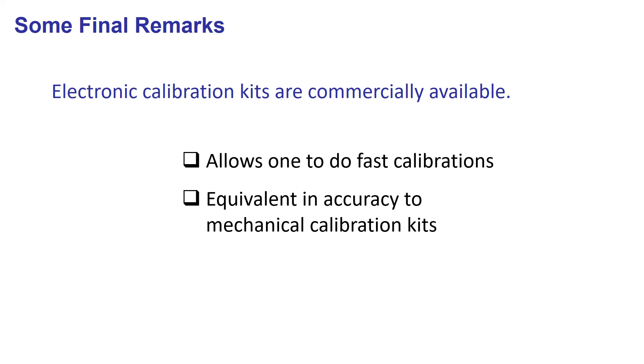The electronic kits are particularly valuable when you need to do frequent two-port calibrations. When working with them, you should check the ratings of maximum input powers, which are sometimes quite low in the cheapest models, and the robustness to electrostatic discharges, which become important if you work regularly in dry environments or with electromechanical devices.